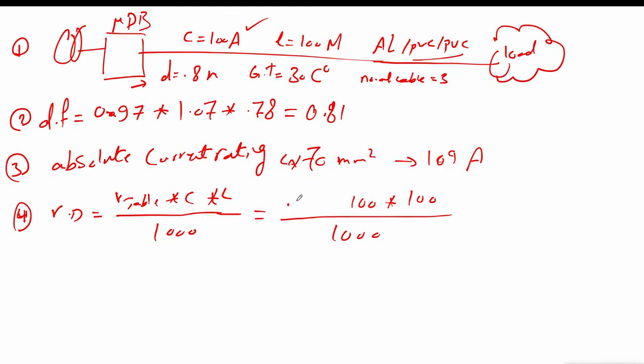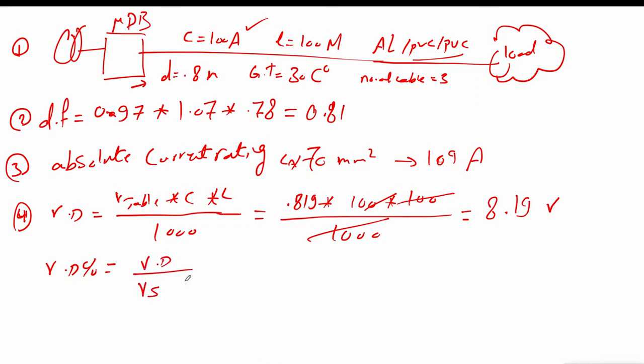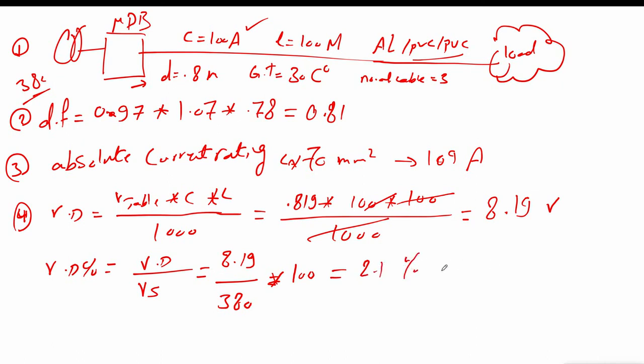The voltage drop value from the table is 0.819 mV/A·m. The total voltage drop equals 8.19 volts. As a percentage: 8.19 ÷ 380 × 100 = 2.1%, which is acceptable as it is less than the 5% limit in the electrical code.